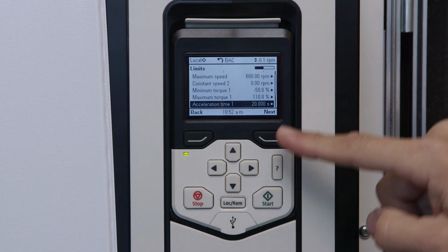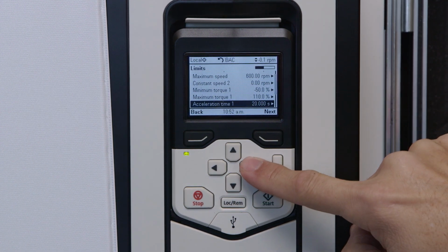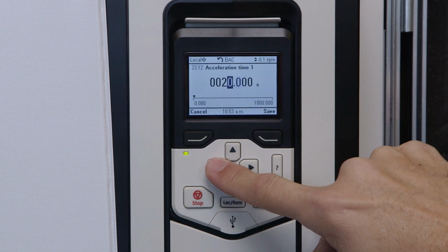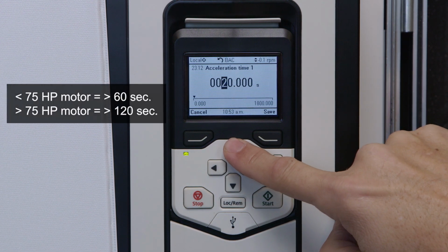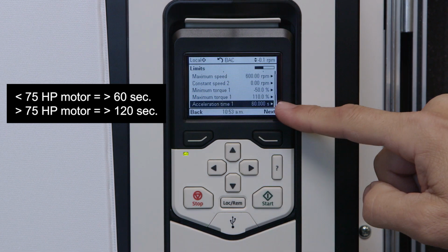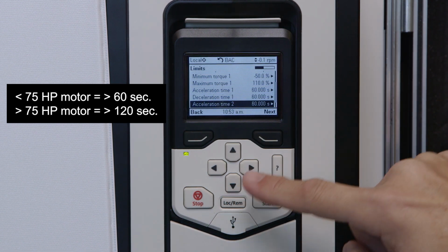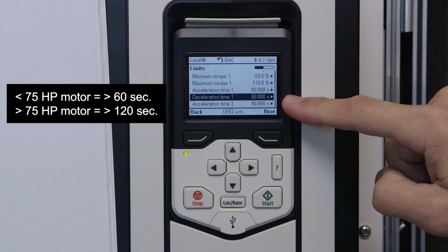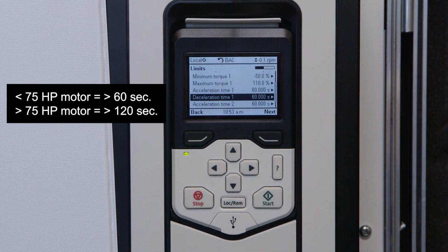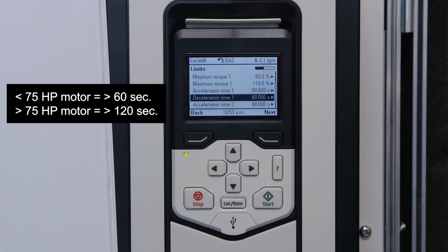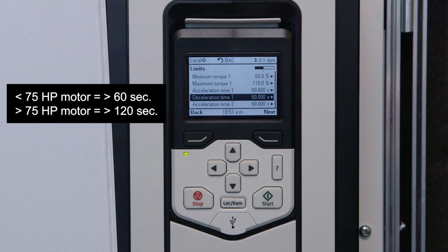Next, let's set the acceleration and deceleration times. A longer acceleration time means slower ramping up. Shorter time means faster acceleration. If the motor is less than 75 horsepower, the acceleration time should be more than 60 seconds. If the motor is more than 75 horsepower, the acceleration time should be more than 120 seconds.